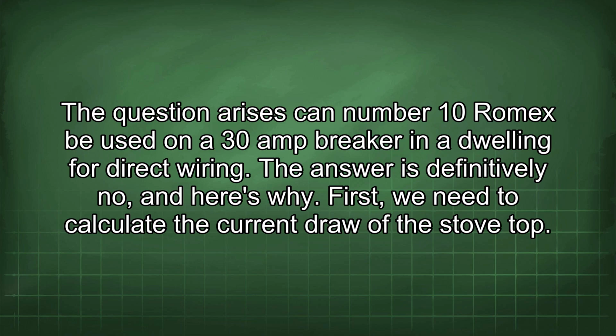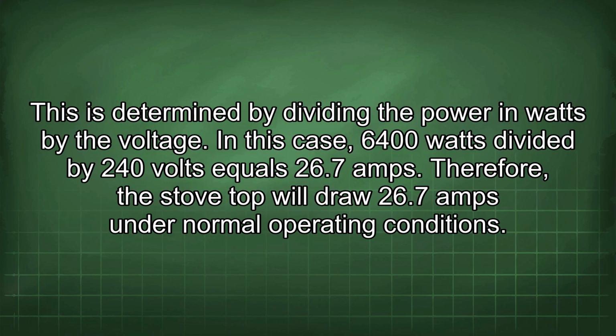First, we need to calculate the current draw of the stovetop. This is determined by dividing the power in watts by the voltage. In this case, 6,400 watts divided by 240 volts equals 26.7 amps. Therefore, the stovetop will draw 26.7 amps under normal operating conditions.